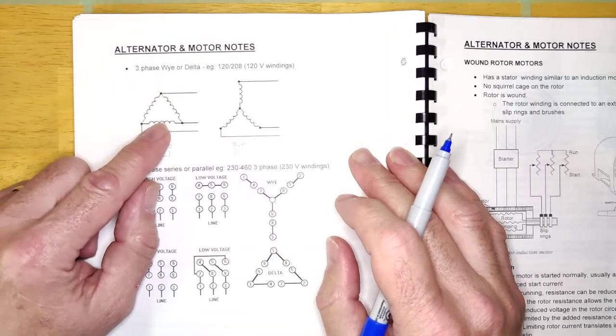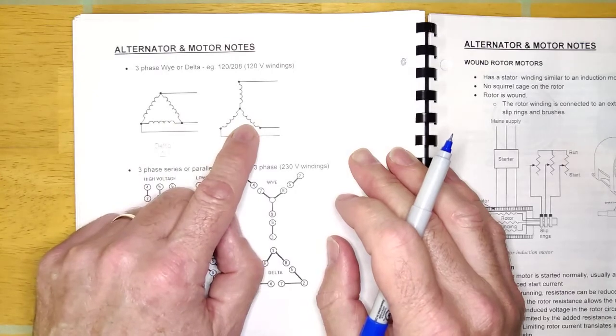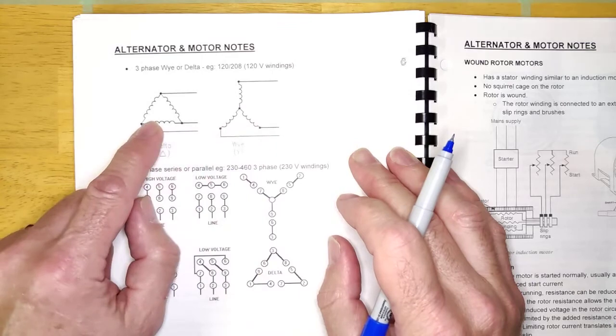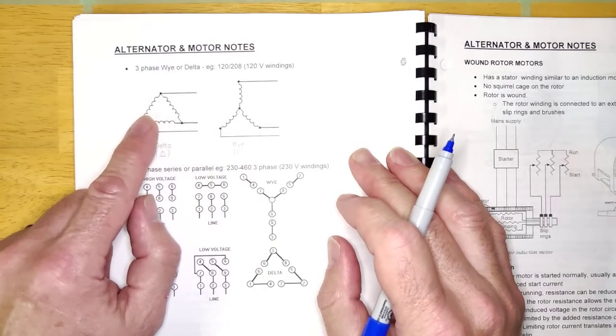And if you just turned this on, you'd get 600 volts to the entire motor, and it would start up and draw a massive amount of current if it was a large motor. And so for a really large motor, sometimes they start them up in Y configuration, and then once they're started in Y, they switch them over to delta on the fly with contactors.